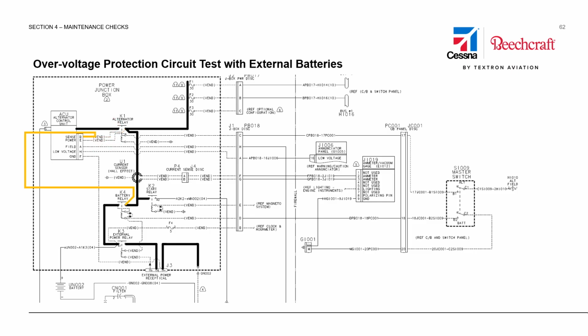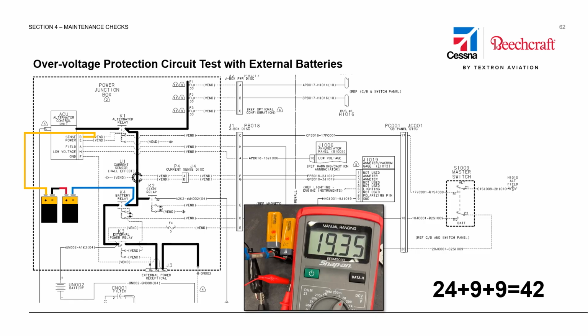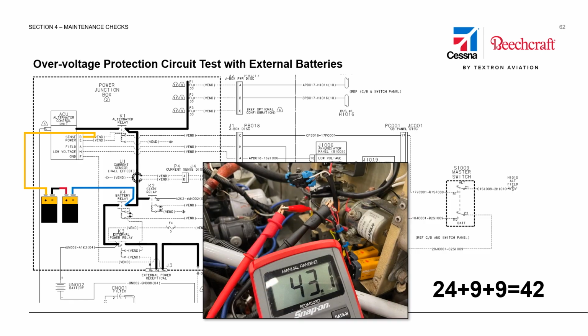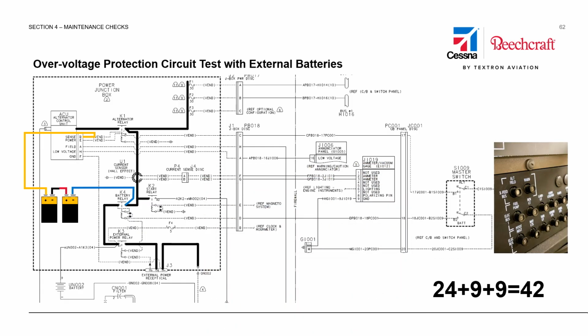The orange sense wire picks off of the same bus, but physically it's connected to the battery relay instead. When we install our overvolt test harness, we add 18 volts to the ship's battery to cross that overvolt threshold. If we have 24 volts at the ship's battery and we add two 9 volts, that will give us about 42 volts of input. Fresh alkaline batteries will be a little bit above that, but that's okay. The reaction time of the ACU is based on the severity of the overvoltage event. A weak ship's battery or weak 9 volts may cause the trip reaction to be slow, or you may observe no trip at all. Proceeding with this test, we'll observe the alternator field circuit breaker.